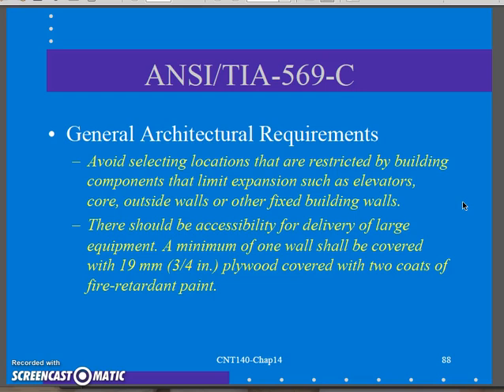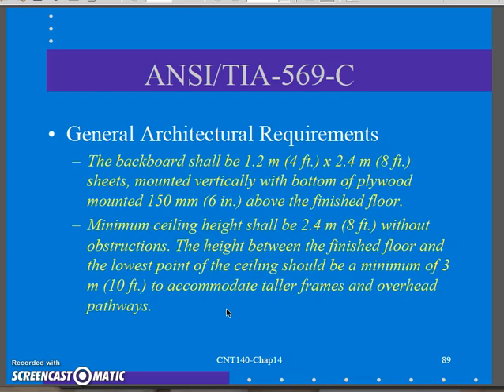There should be no room-to-expand issues. This should be a good location for my data, allowing for expansion if need be — not sharing outside walls or other fixed building walls. There should be accessibility for delivering large equipment, room to get closet equipment in and out, and one of the walls should be covered with three-quarter-inch plywood with two coats of fire-retardant paint. That way you can anchor things like 66 blocks and 110 blocks on the wall for your phone system, or terminate an ISP connection box on the wall.